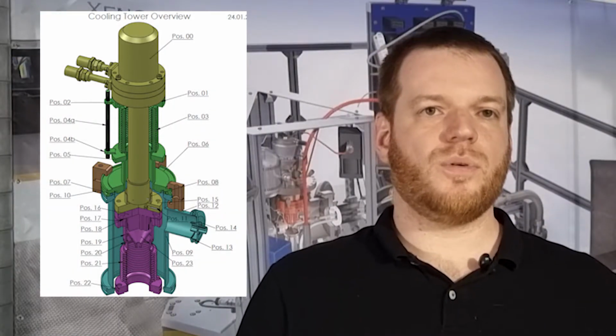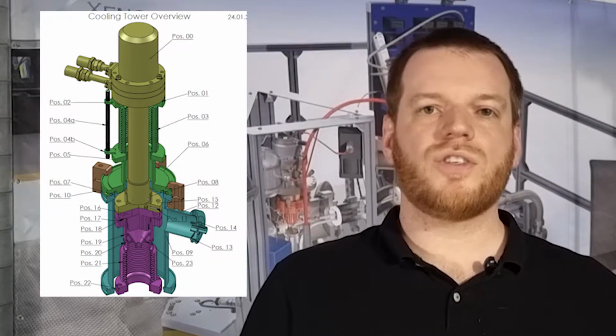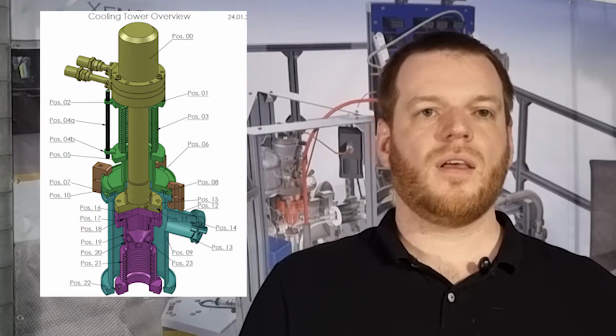Helium gas is slowly compressed and expanded by a piston, exchanging gas at one end of the tube in the heat exchanger. The cold end of the tube is thermally coupled to a copper cold head onto which the xenon is liquefied. Again, the PTR provides a set amount of cooling power, and we control the temperature of the cold head with a heater strip and a PID controller.